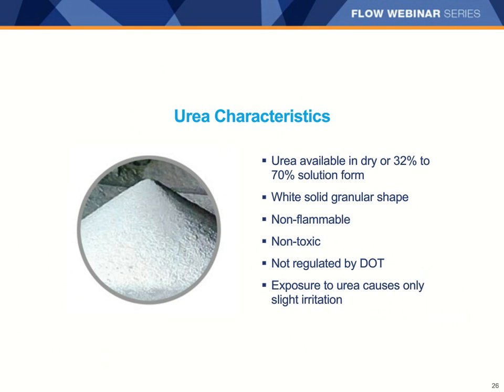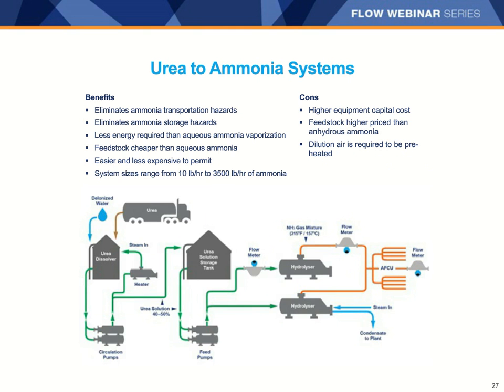Last, we have urea. Safety is the principal advantage of a urea-based ammonia system. Urea is non-toxic and not regulated by DOT. In a urea to ammonia system, as shown here, mass flow meters are used on the inlet and outlet of the hydrolyzer for mass balancing, as well as on the ammonia vapor injection for the SCR process. Once again, the precise flow measurement of that ammonia vapor is critical because it assures the proper ratios, avoiding under as well as over injection.